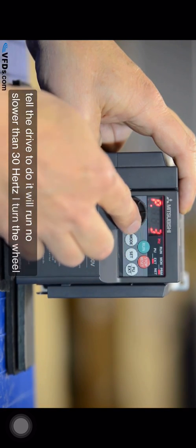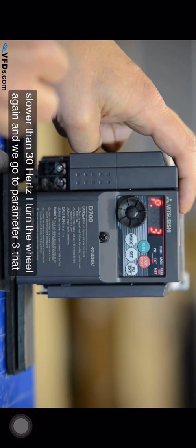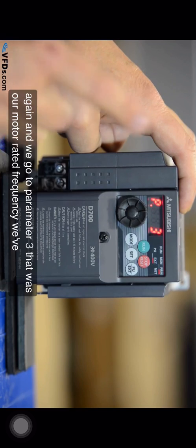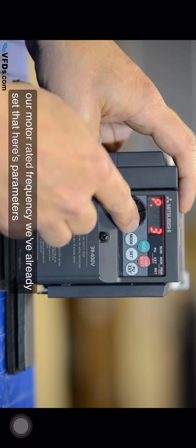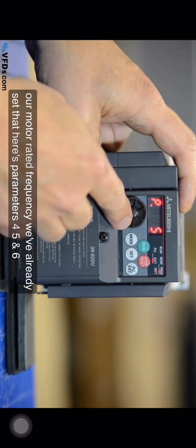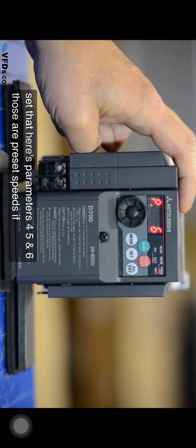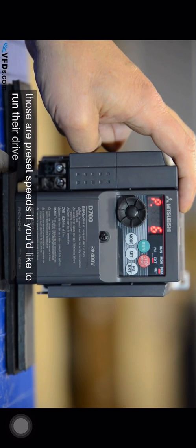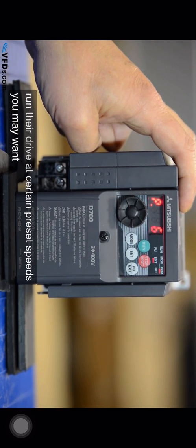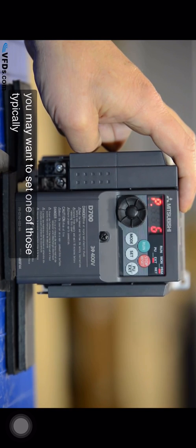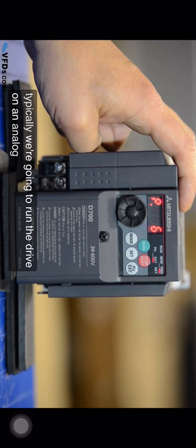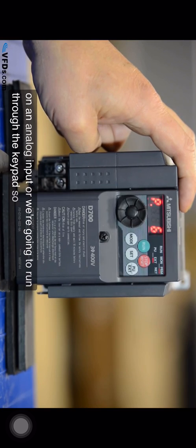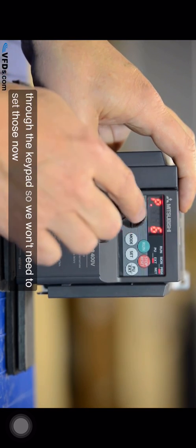I turn the wheel again and we go to parameter three. That was our motor rated frequency. We've already set that. Here's parameters four, five, and six. Those are preset speeds. If you'd like to run the drive at certain preset speeds you may want to set one of those. Typically we're going to run the drive on an analog input or we're going to run through the keypad so we won't need to set those.